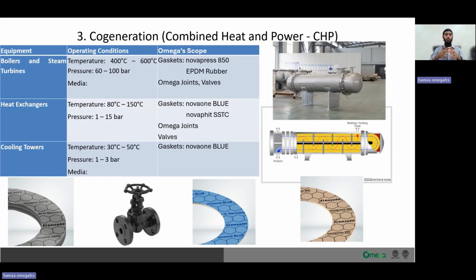So the combined heat and power cycle works in the following way. The fuel input, a primary fuel source like natural gas, is used to power an engine or turbine, which is then connected to electricity generators. Then this spent energy from the medium is reutilized with the help of heat recovery. The heat that is a byproduct of this process, from exhaust gases and engine cooling, is reutilized. Thermal energy is recovered. This recovered thermal energy is used to provide steam, hot water, or to produce chilled water for cooling and in other industrial processes.